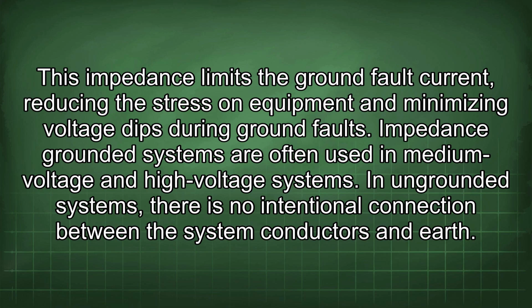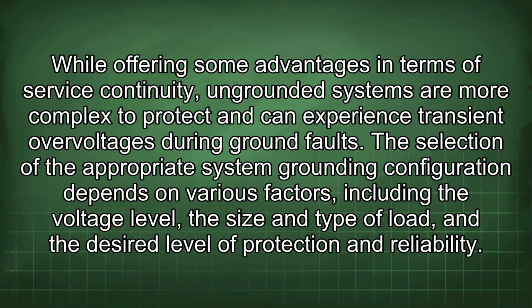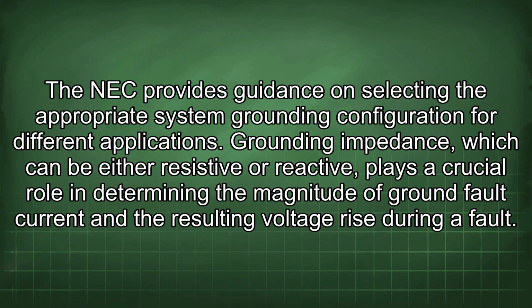In ungrounded systems, there is no intentional connection between the system conductors and earth. While offering some advantages in terms of service continuity, ungrounded systems are more complex to protect and can experience transient overvoltages during ground faults. The selection of the appropriate system grounding configuration depends on various factors, including the voltage level, the size and type of load, and the desired level of protection and reliability. The NEC provides guidance on selecting the appropriate system grounding configuration for different applications.